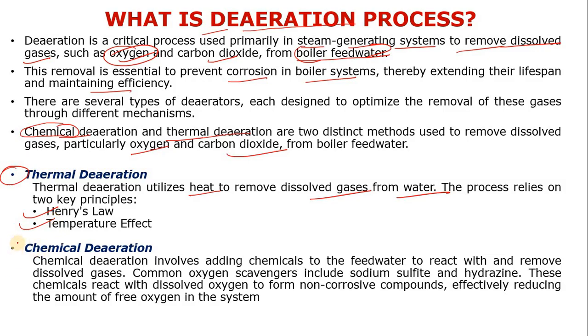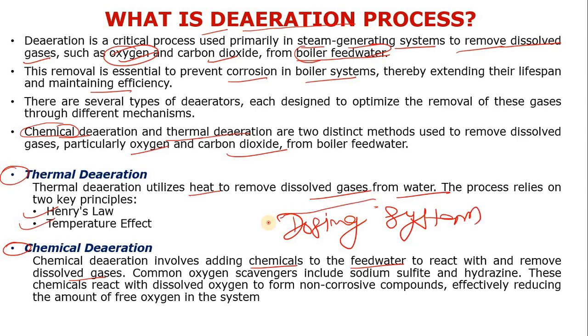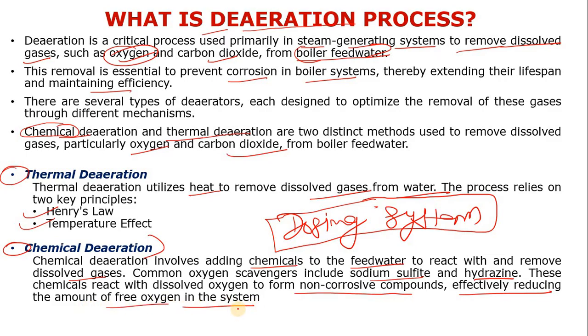Chemical de-aeration means adding chemicals to the feed water to react with and remove dissolved gases. If you are a process engineer preparing a boiler P&ID or steam generating P&ID, you will see a dosing system with reciprocating pumps — positive displacement pumps — used for chemical de-aeration. Common oxygen scavengers like sodium sulfite or hydrazine are injected directly into the steam drum, where they react with dissolved oxygen to form non-corrosive compounds.